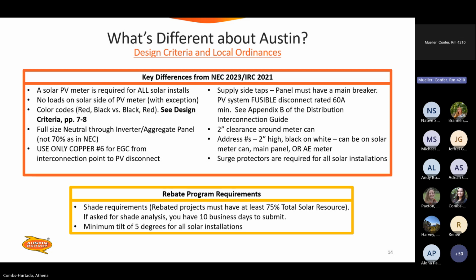So your panel's got to have a main breaker. If you're doing a supply side tap, your panel's got to have a main breaker regardless. And your disconnect will need to be fusible and rated a minimum of 60 amps. So even if you've got a 20 amp system and you have to use fuse reducers and all that, because it's technically service equipment, it's got to be a 60 amp rated disconnect. You need 2 inches of clearance around all meter cans.